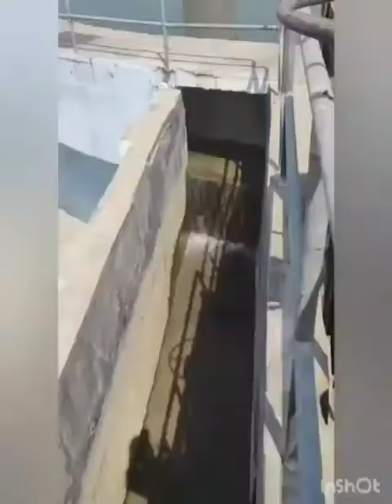In the clarifier, the water is treated with alum and polyelectrolyte to maintain pH values and turbidity. With the help of the agitator and flocculator, it is thoroughly mixed and the sludge is sedimented, and the clear water is collected in the clear water sump. From the clear water sump, using clear water pumps of about 1000 cubic meter capacity, the treated ash recovery water is pumped to the ash water sump located in the ash handling system. By this, the ash water is recovered without letting it into the environment. The water recovered from the ash water recovery pump house is about 20 to 30%.